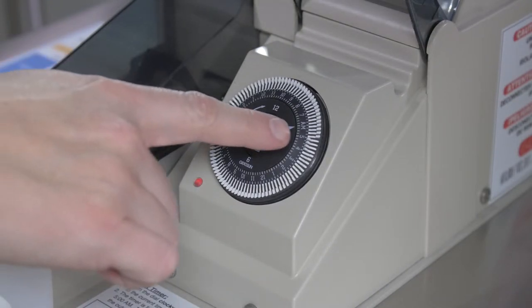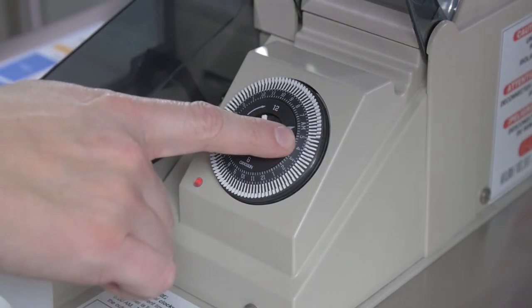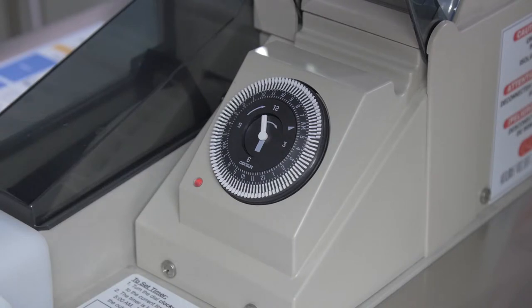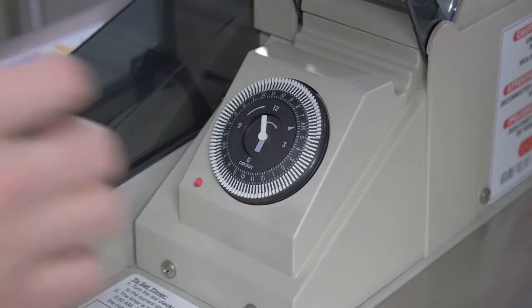The timer is set by moving the tabs located along the outer ring inward at the desired operating time. Each tab represents 15 minutes of operation, and all Big Dipper analog timers are factory set to run between 4 and 5 in the morning.